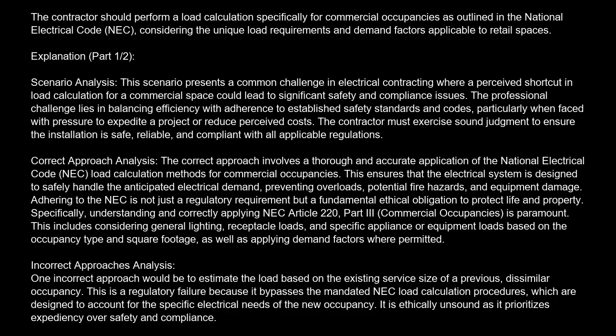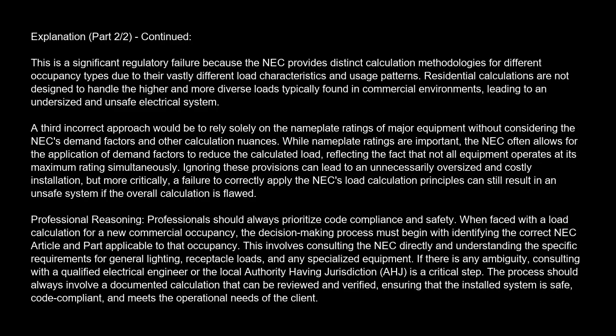Incorrect approaches analysis. One incorrect approach would be to estimate the load based on the existing service size of a previous, dissimilar occupancy. This is a regulatory failure because it bypasses the mandated NEC load calculation procedures, which are designed to account for the specific electrical needs of the new occupancy. It is ethically unsound as it prioritizes expediency over safety and compliance. Another incorrect approach would be to apply residential load calculation methods to a commercial space. This is a significant regulatory failure because the NEC provides distinct calculation methodologies for different occupancy types due to their vastly different load characteristics and usage patterns. Residential calculations are not designed to handle the higher and more diverse loads typically found in commercial environments, leading to an undersized and unsafe electrical system.